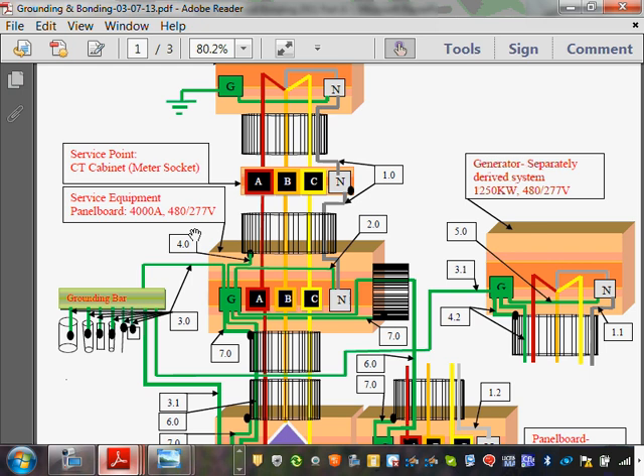Now what happens if you lose the neutral and you only have 220 to ground? Open circuit. Do you burn anything? Nothing. And that's in single phase. In a three-phase system, they come here and measure your impedance. If your impedance is 5 ohms or less, they allow you to tie to the neutral. Or actually less than 5. If it's less than 5, they allow you to tie to neutral. 5 or less, you have to maintain 5 or less.